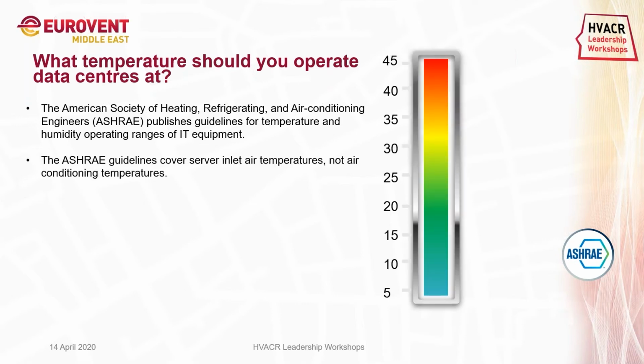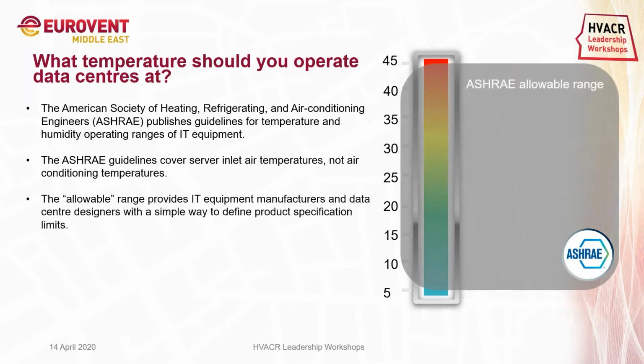So the main point here is the ASHRAE guidelines cover the server inlet air temperatures. That is the temperature entering the servers or entering the racks, not the air conditioning temperatures, not the return air temperatures of the air conditioners. So we need to look at that. The temperatures mentioned in this section are the server inlet temperatures. ASHRAE has introduced two ranges, one allowable range and a recommended range.